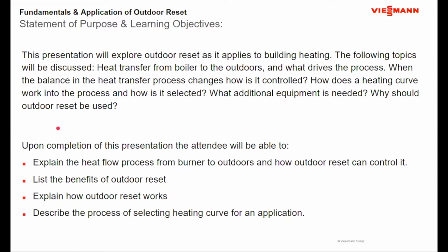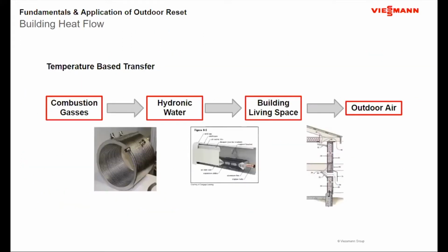Now, when we look at outdoor reset, it really is part of the process of heating a building. And I always laugh when I start to think about this, having now two 20-some-odd-year-old sons. One of the things I'd always tell them when they left the door open is, close the door, we're not paying to heat the outdoors. When in reality, when you look at the heat loss of a building, we are actually paying for heating the outdoors because of the heat loss of the building, but the goal is to minimize that in the process.